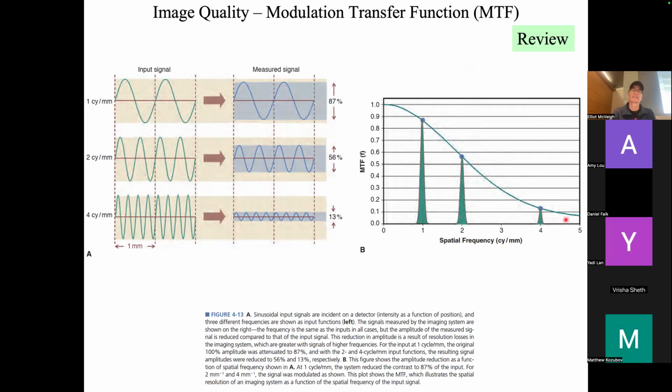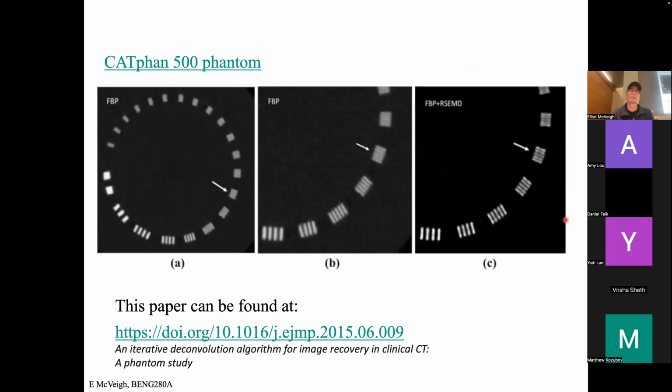So it's up to you actually to measure it, right? They say, oh, our scanner does this, and you say, thank you very much. And you take your phantom to the scanner and find out what it actually does. These are probably pieces of aluminum embedded in perspex or plastic.